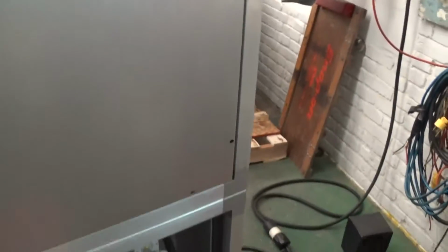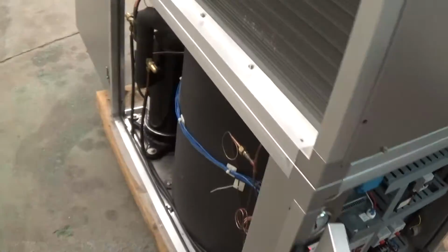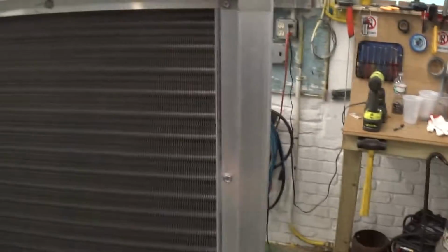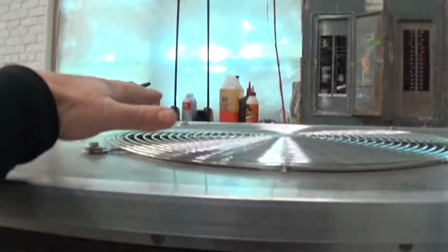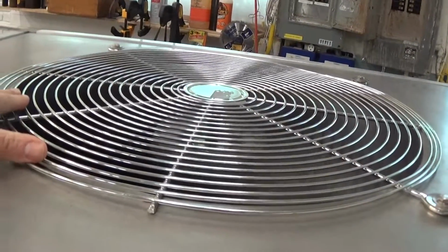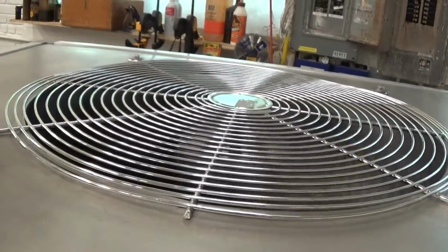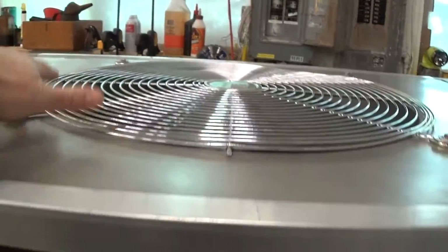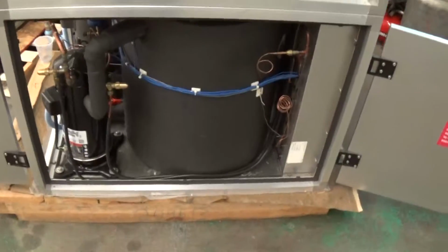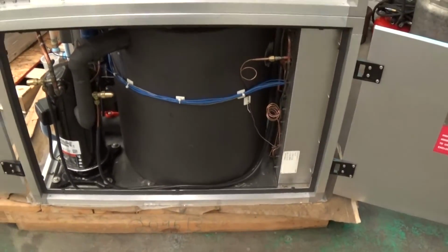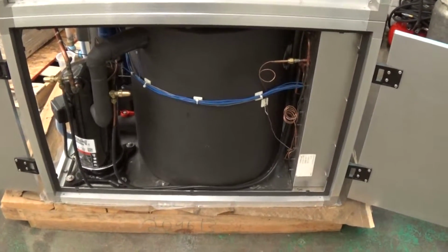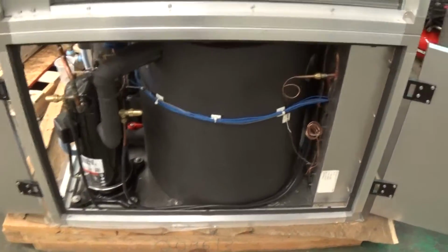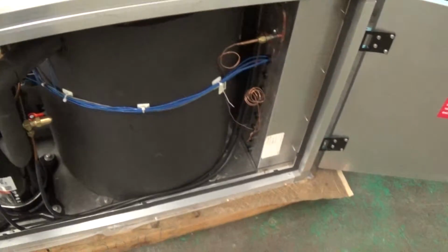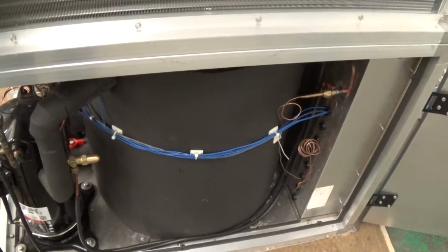All right. So let's talk about some of the components of the unit. We love this frame design here. Right now you can hear the fan, or see the fan kind of cycling speed on and off a little bit based on its load. You have a nice insulated reservoir here. The heat exchanger, the refrigerant to fluid heat exchanger, is actually inside that insulated tank.